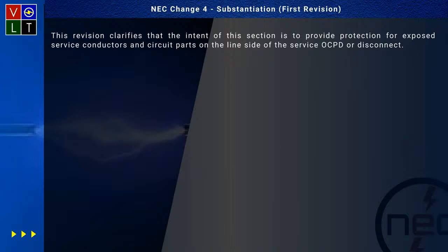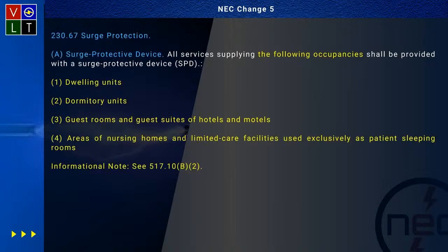And that's what I'm saying. Those are still energized. So that barrier is not going to protect you from an arc blast. Okay. Yeah, and they do have some pretty good barriers in there, but you have to just be careful when you're in those service equipment. Sure. Now, this is interesting because they're talking about surge protection devices again.